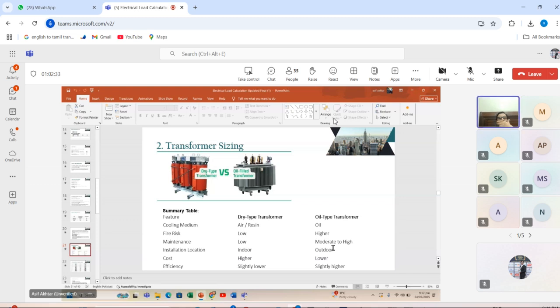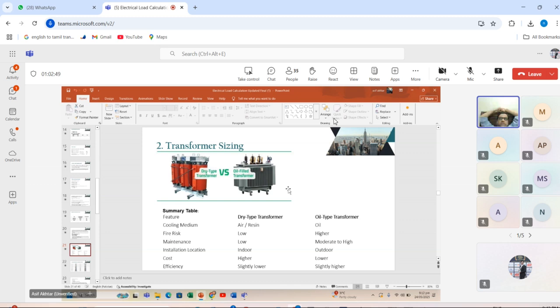Transformer sizing. That page is waiting for transformer sizing. We have two types of transformer: one is the dry type transformer and the other is the oil filled transformer. It depends upon your budget, and both have advantages and disadvantages. Mainly in our high-rise buildings, we use the dry type transformer. Its main features are that the fire risk is very low, the maintenance cost is very low, and the cooling medium is air, whereas in the oil type transformer the cooling medium is oil, and the cost of the oil type transformer is lower. So we can use either transformer depending upon the budget.